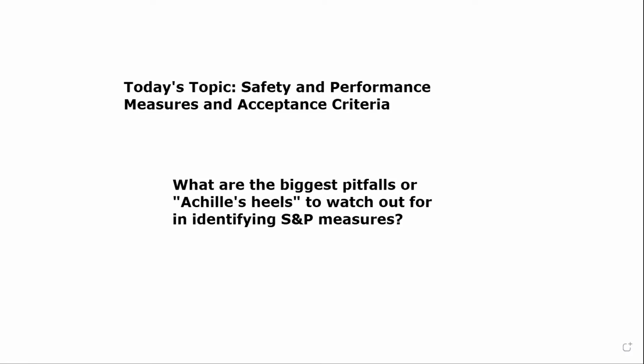And if those objectives are very narrowly written and don't pertain to your competitors, you're going to have a hard time finding acceptance criteria. So don't do that. Another pitfall, or an Achilles heel, might be that the safety and performance objectives are not meaningful to the intended purpose or the population, and as I've said, and most important, there's no competitor data available. So those are some common watch-outs when you're choosing your safety and performance objectives.